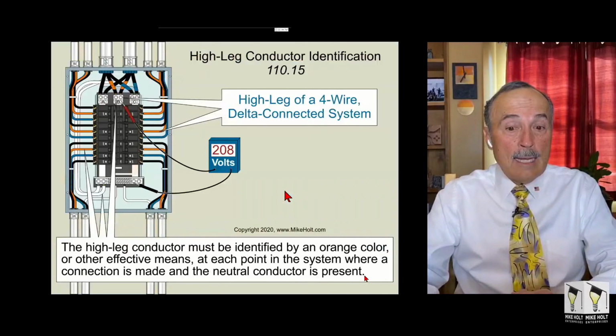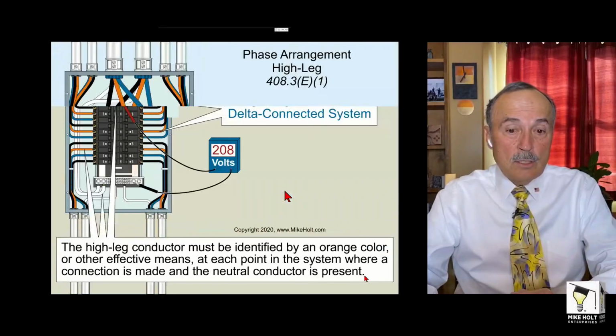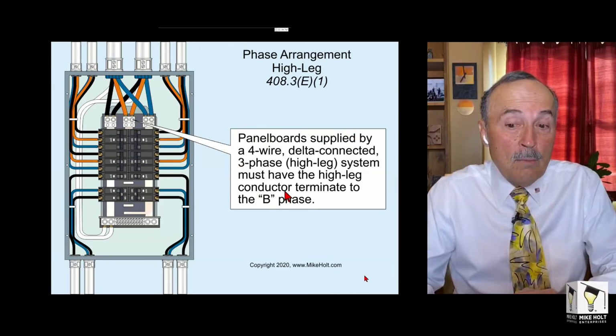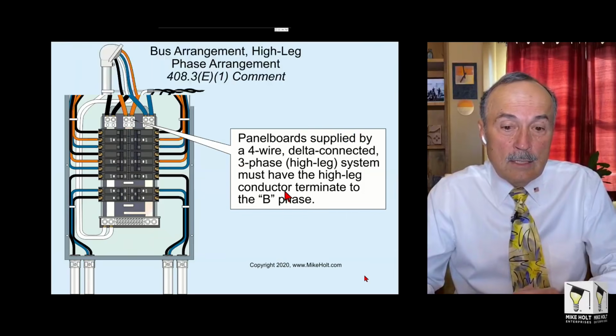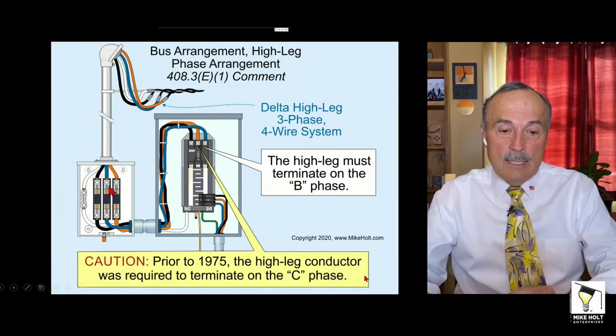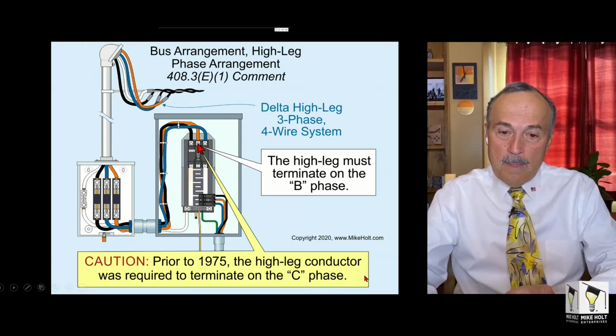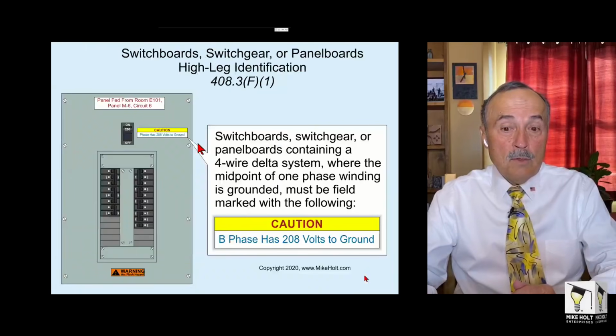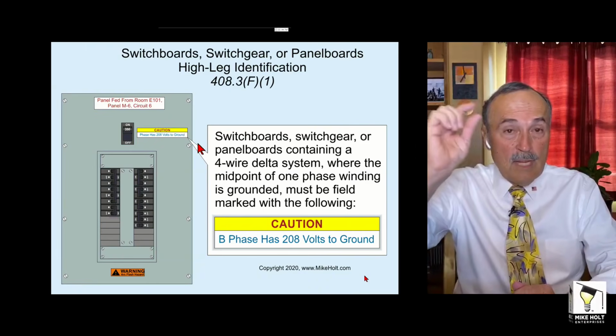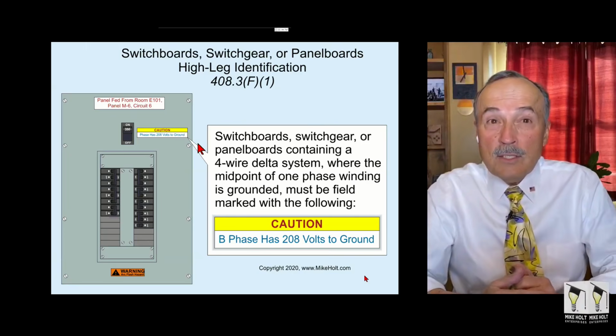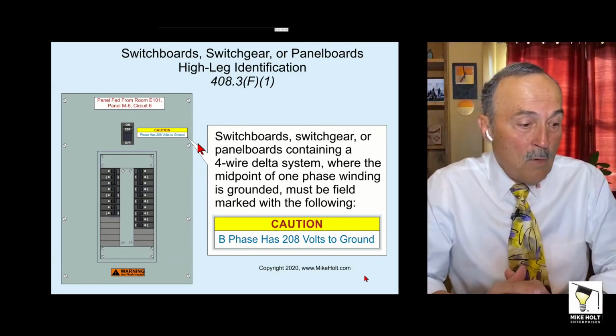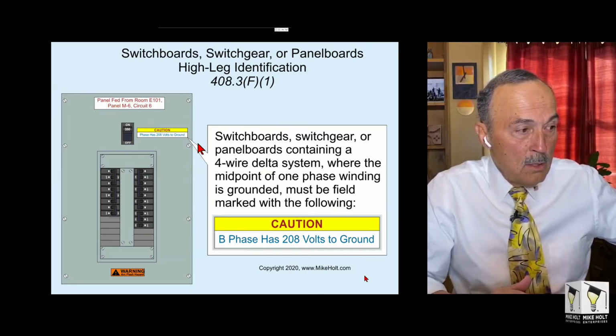And then high leg color, 110.15, orange. You terminate in panel boards on the B phase. And in the meter cans, it's going to be on the C phase. This is a panel board that would be on the B phase. And at the panel board, you have to make sure you put some kind of identification that the B phase is rated 208 volts.